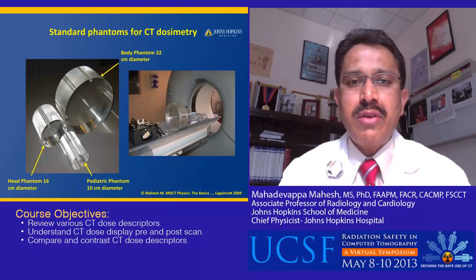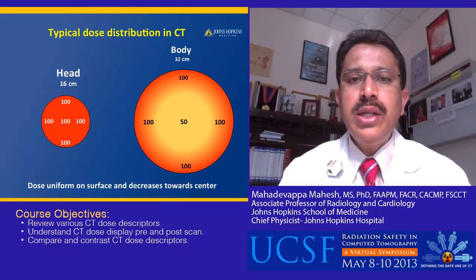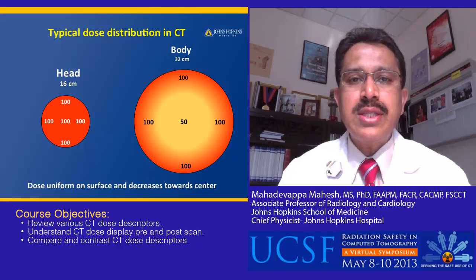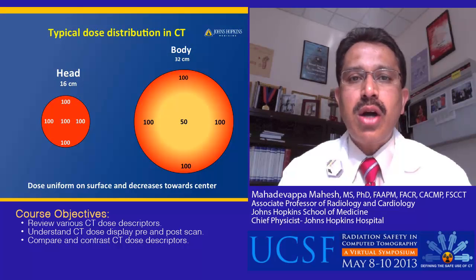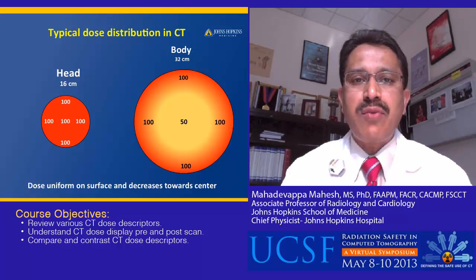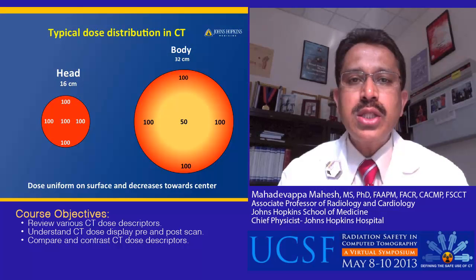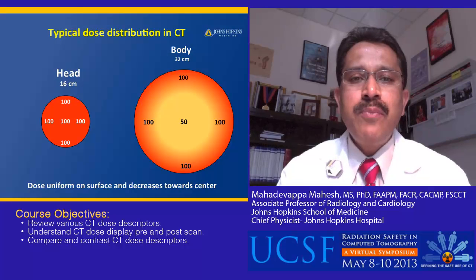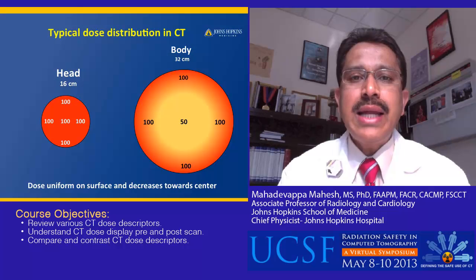We also use a 10-centimeter diameter lucite phantom called the pediatric head phantom. When you look at the dose distribution in this phantom, if the object size is small, the measurement done on the surface is the same as the measurement done at the center. However, if it is the larger phantom such as the body phantom, the surface dose is almost twice that of the center. Because of this variation, the measurement done at different locations of the phantom is variable, and that is accounted for in the development of the CT dose descriptors.